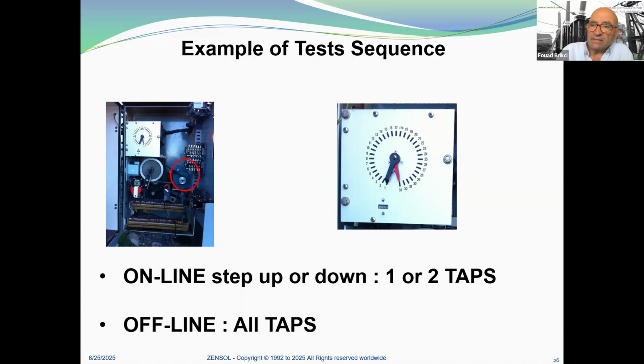For offline tests, we record all taps to get a reference. And we recommend to get a reference of each transformer with OLTC of your park of transformers. With these recordings, you could establish your action maintenance plan for all your transformers with OLTC. In fact, you can reach the stage of predictive maintenance because you know which part is going to fail.